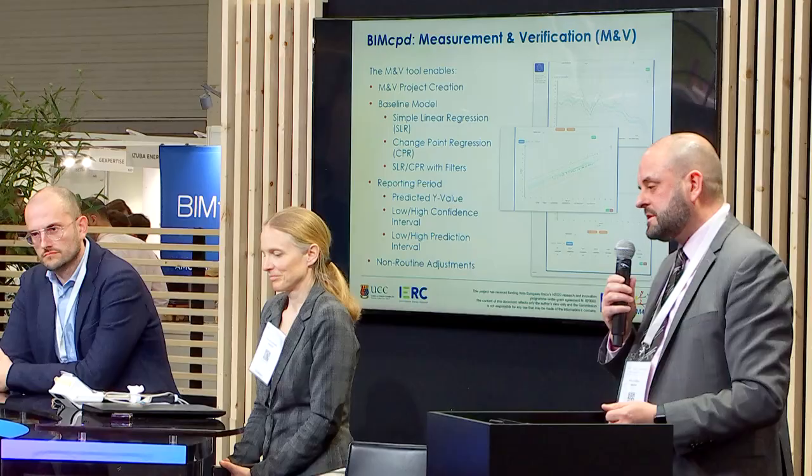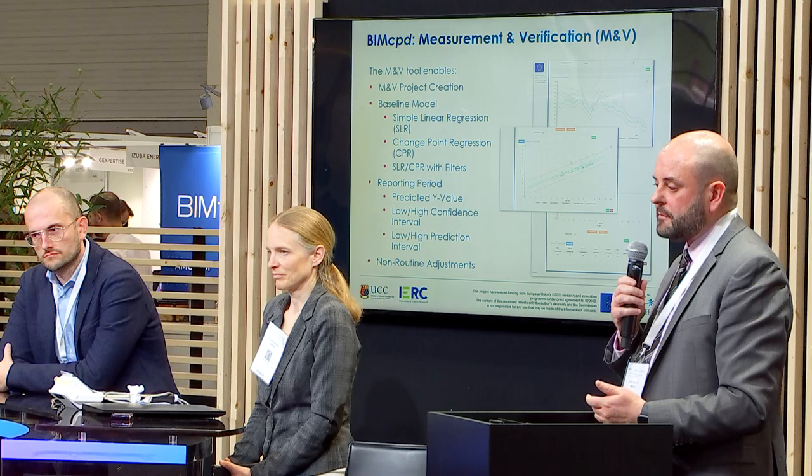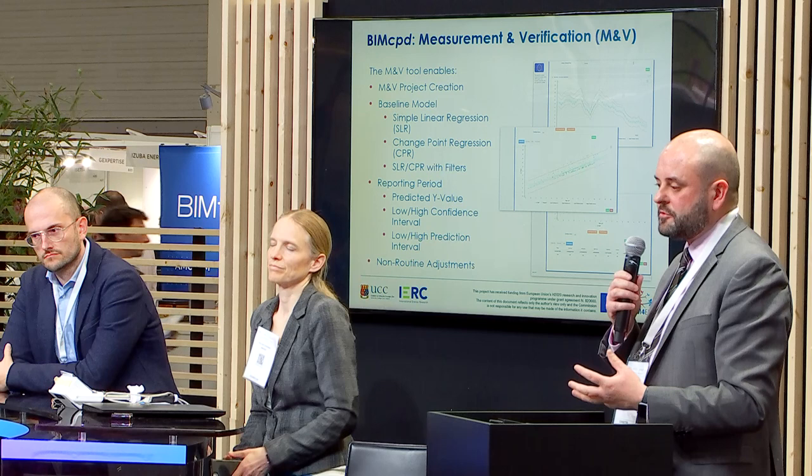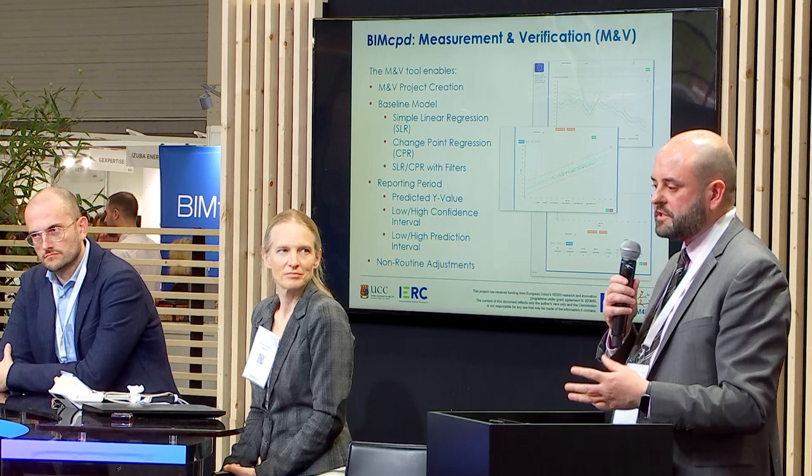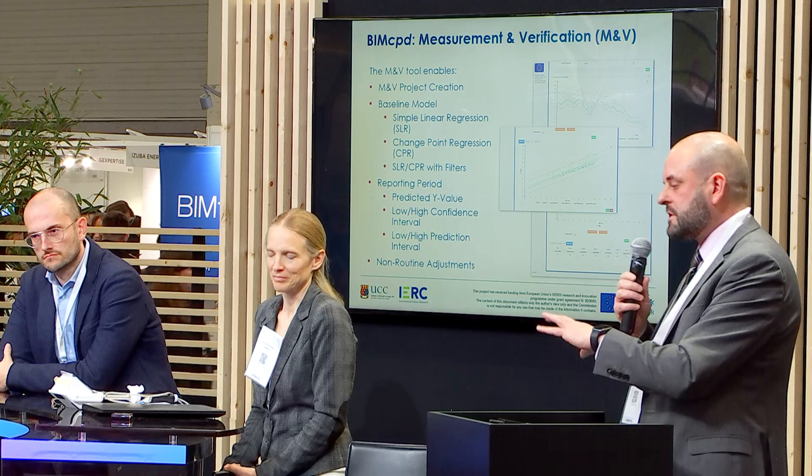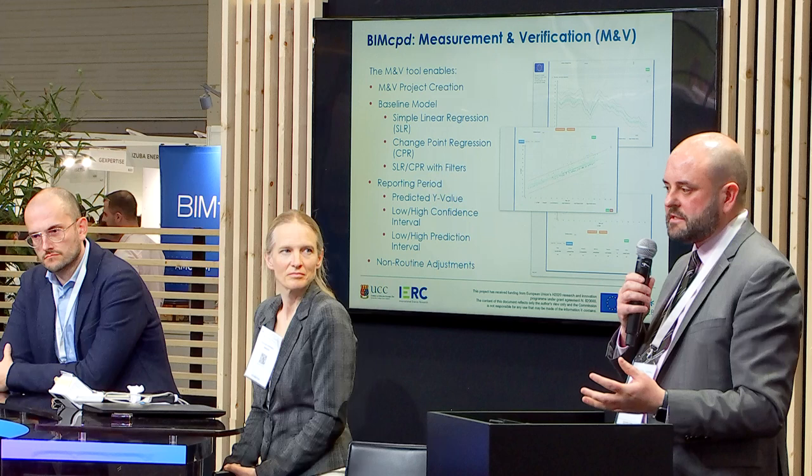In addition to the data viewer, there was also the measurement and verification tool, which tied into another part of BIM4EEB. This tool runs almost as a standalone tool, where you can do a measurement and verification project by filling in the details, what type of M&V project it is, and creating the baseline model, choosing whether it's a simple linear regression, a change point regression, or even a simple linear change point with filters. So it's up to the user to make those adjustments to the data to create the baseline. After the renovation is complete, you carry out a reporting period and then analyze the differences between your baseline and your reporting period to arrive at your savings amount or energy reduction amount. It depends on what you're trying to model.